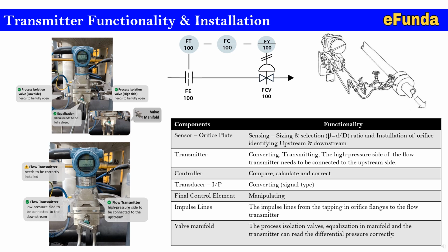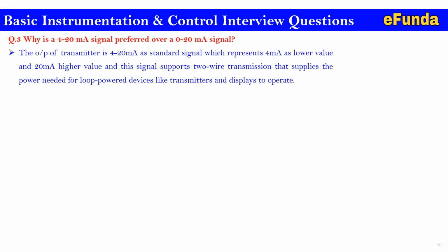Controller, which is used to compare, calculate and correct the action. Transducer, that is the I2P, converting the signal type from current to pressure. Final control element is the manipulating element. The impulse line runs from the tapping in the orifice flanges to the flow transmitter. Valve manifold, the process isolation valve, and the equalization valve in the manifold, so the transmitter can read the differential pressure correctly. Question 3. Why is a 4 to 20 milliamp signal preferred over a 0 to 20 milliamp signal?